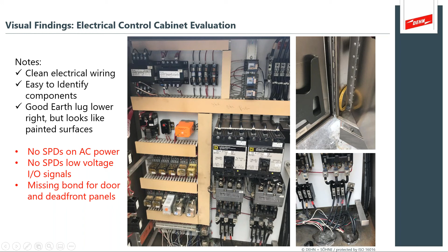Visual findings at the control centers. Again, we're looking for those same types of things. There's a lot of equipment in here that can suffer electrical damage. We're looking for AC surge protection. We're looking for SPDs on the emergency lighting circuits. We're looking for SPDs on the IO lines, the control lines, so that this operation is robust and can withstand lightning damage events.